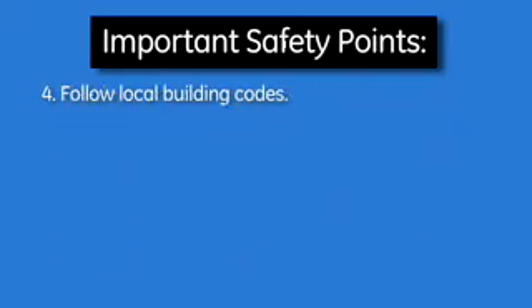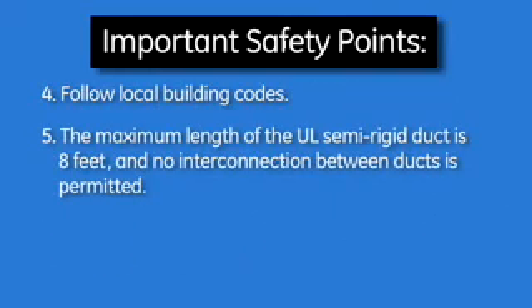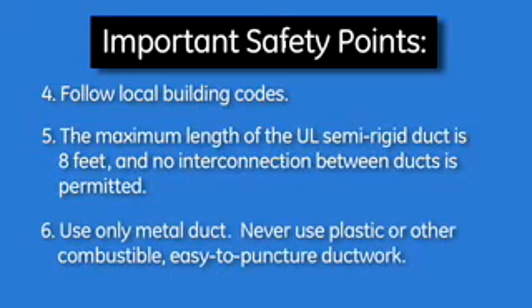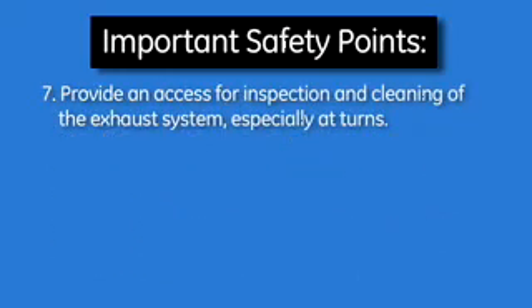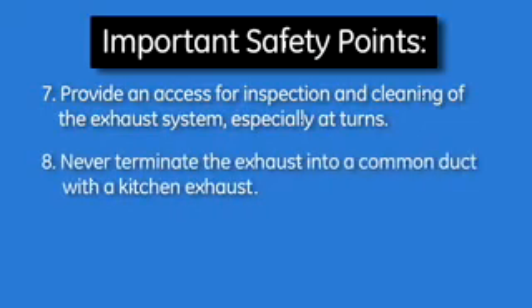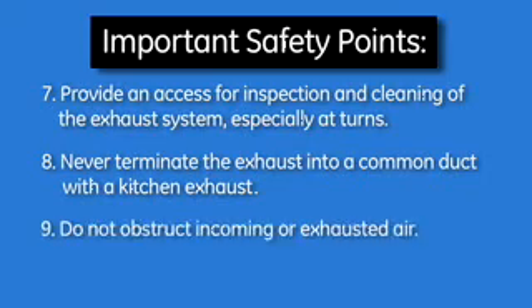Follow local building codes. The maximum length of the UL semi-rigid duct is 8 feet and no interconnection between ducts is permitted. Use only metal duct. Never use plastic or other combustible, easy-to-puncture ductwork. Provide an access for inspection and cleaning of the exhaust system, especially at turns. Never terminate the exhaust into a common duct with a kitchen exhaust. And finally, do not obstruct incoming or exhausted air.